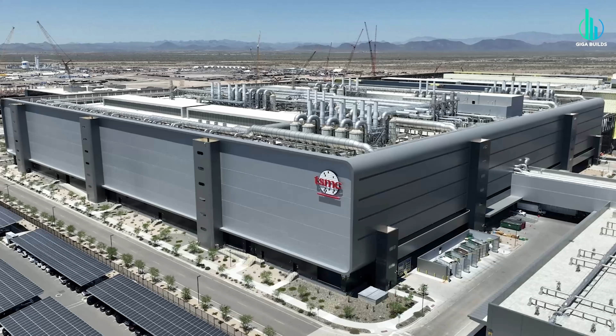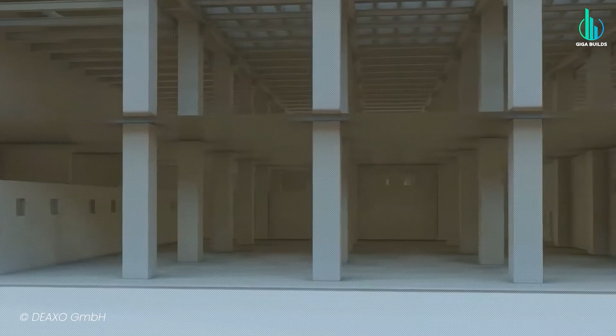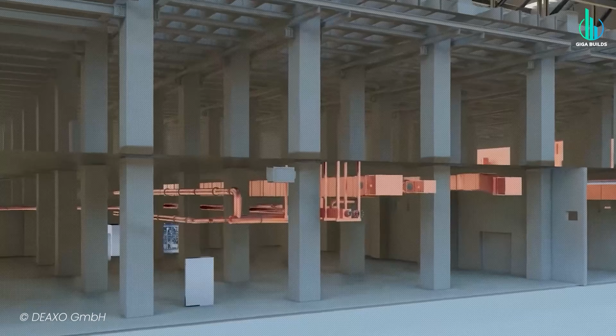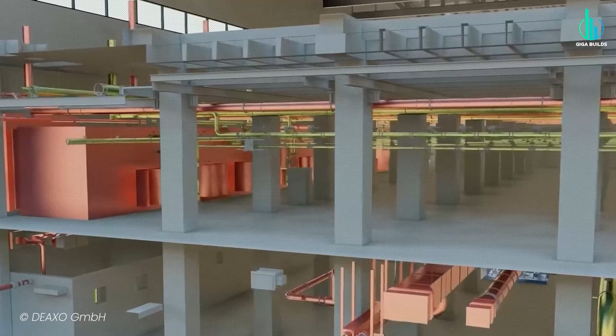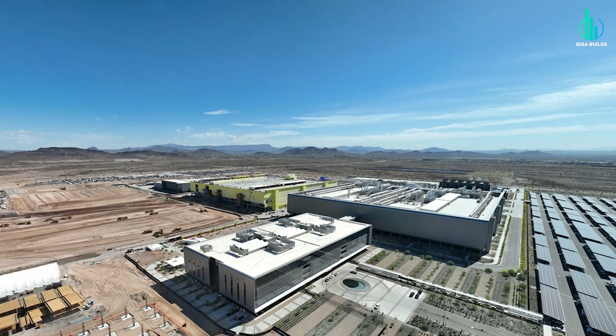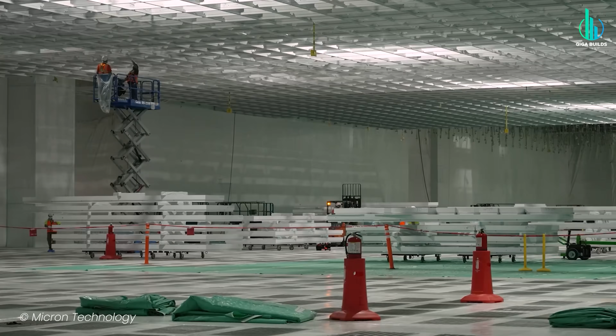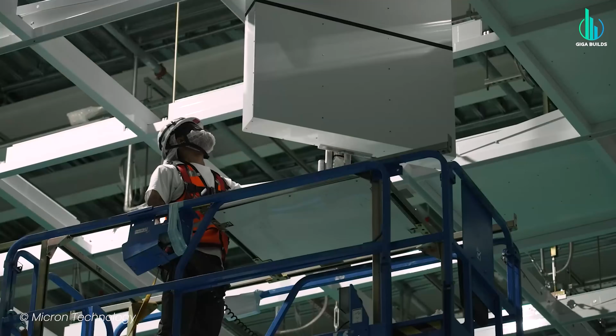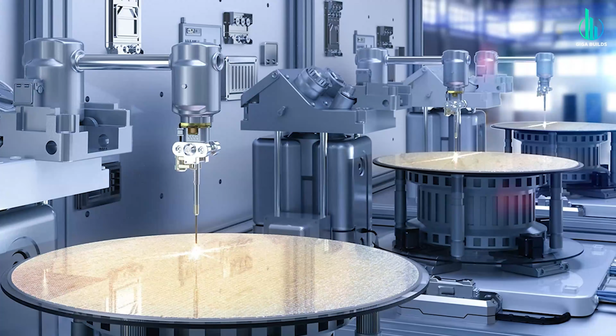A semiconductor fab is a building wrapped around another building. Utility corridors beneath the floor. Mechanical levels above the clean room. Pipes stacked in layers. Water, chemicals, vacuum, exhaust, nitrogen, process gases, cooling lines, electrical systems. Thousands of connections feeding thousands of tools. What looks like one factory is actually a vertical network of manufacturing systems. The clean room is only the surface. The machinery supporting it fills the space above, below, and around every production line.